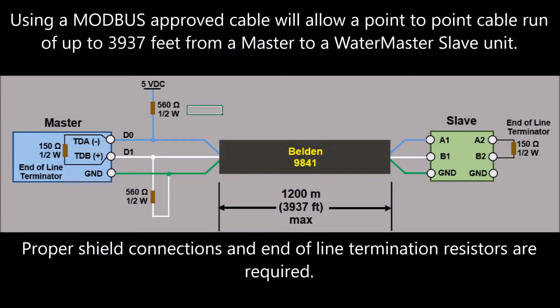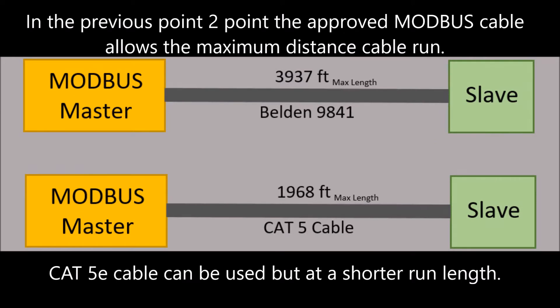Using a Modbus approved cable will allow a point-to-point cable run of up to 3,937 feet from a master to a Watermaster slave unit. Proper shield connections and end-of-line termination resistors are required. CAT-5E cable can be used but at a shorter run length.